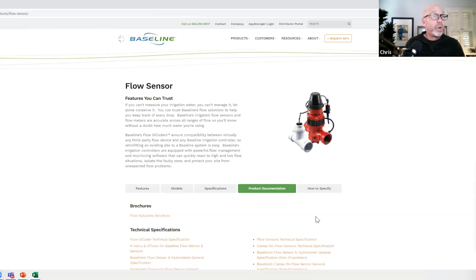Question 14: Is there a document that shows the minimum flow rate for the IDFS flow sensors? This is a clamp-on flow meter product we have, available in a wide range of sizes from about a quarter inch up to 8 inch or larger. It uses ultrasonic technology, so it reads a very broad range of flows through the pipe. If you look on the website in the Flow section, go to the tech spec for the IDF flow sensor, you'll see that for different sizes it shows the flow range associated with them, though not all sizes. But to answer that question, we really need to know what size flow sensor we're dealing with.